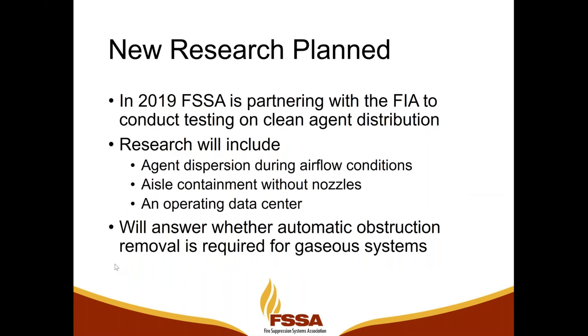So one of the questions that's still out there in the minds of many suppression experts is this: gaseous systems, we know, penetrate many shielded enclosures and data center racks to be able to get into the rack and address fires. That's why we don't have to put nozzles right in the rack. So we anticipate that some of that gas will flow through those racks into the contained subvolume, but we don't really have proof of that.